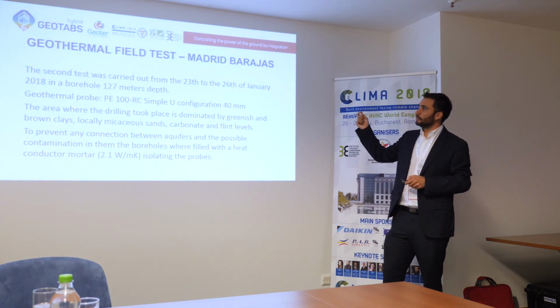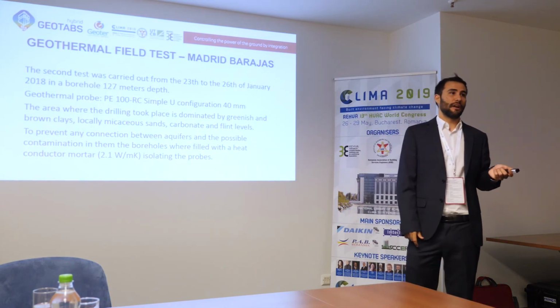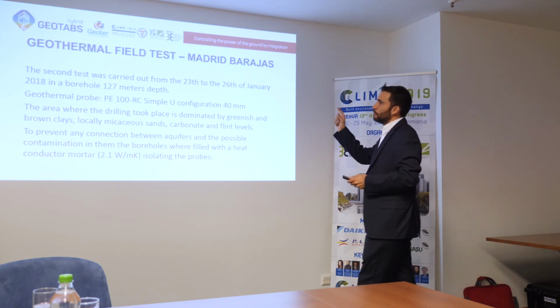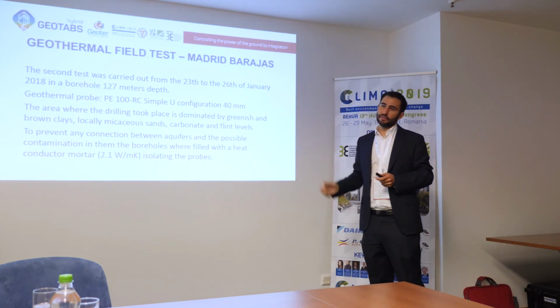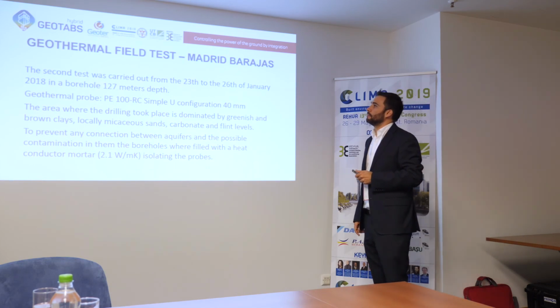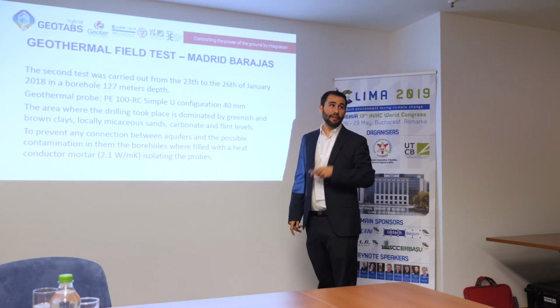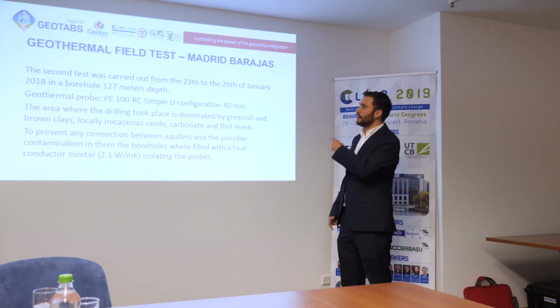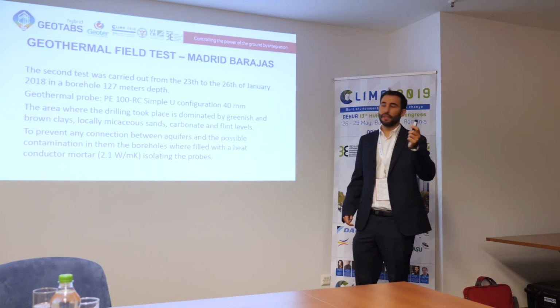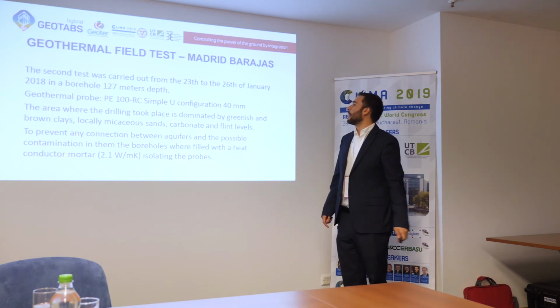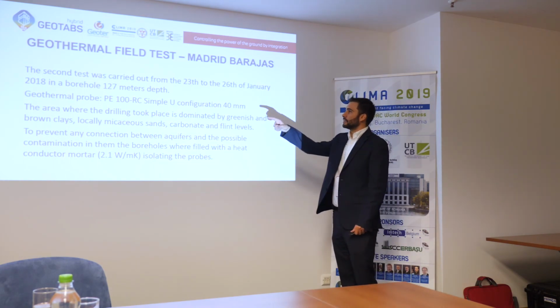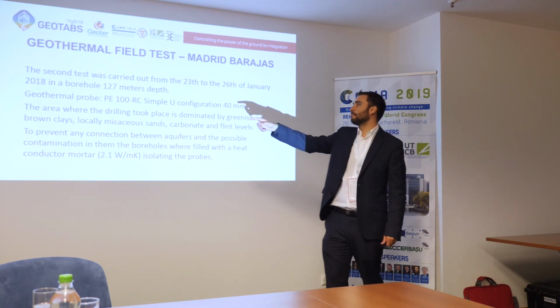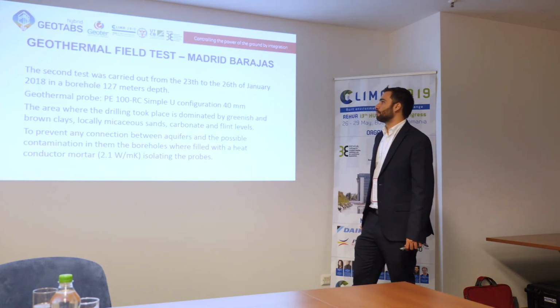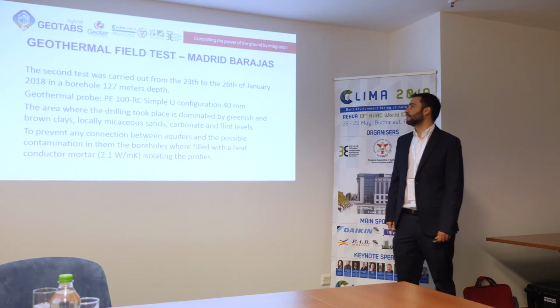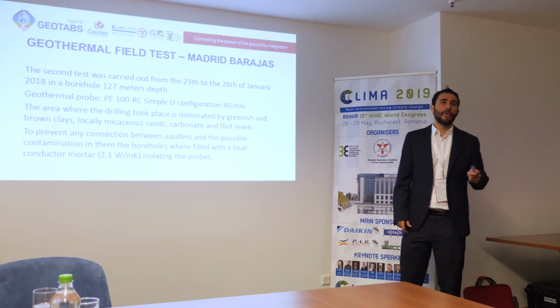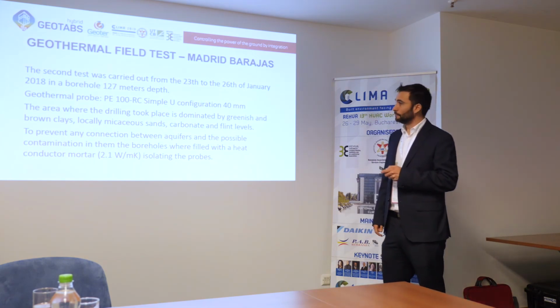And the second test is in Madrid-Barajas Airport. In Madrid-Barajas Airport, during January 2018, again in a borehole 127 meters deep with a geothermal probe, again polyethylene 100 simple U configuration, 40 millimeters. In this case, the area was dominated by greenish and brown clays, locally micaceous sands, carbonate and flint levels. And we filled the borehole again with a high conductivity mortar.